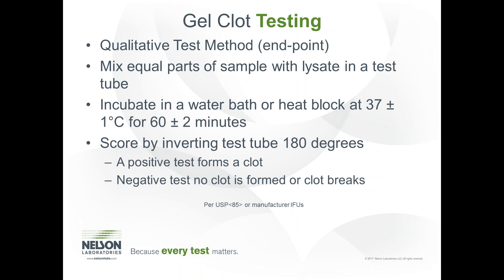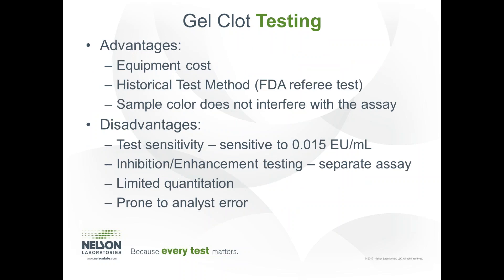The gel clot test was the first that was developed. It is a qualitative test rather than a quantitative test, and it's relatively straightforward. You mix equal parts of the lysate and the sample extract in a test tube and incubate at 37°C ±1 for 60 ±2 minutes, then score the test by inverting the test tube 180 degrees. If the clot forms, it's positive; if the clot breaks, it's negative. Advantages include low equipment cost, it is considered the FDA's historical referee test, and sample color does not interfere. Disadvantages include limited sensitivity, inhibition enhancement testing required for validation is a separate assay, limited quantitation, and it is prone to human error, as analysts inverting test tubes can accidentally break the clot.